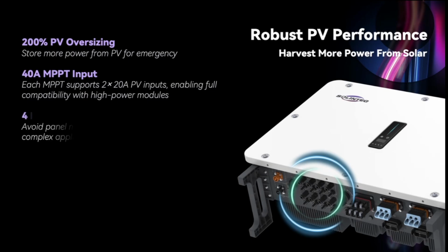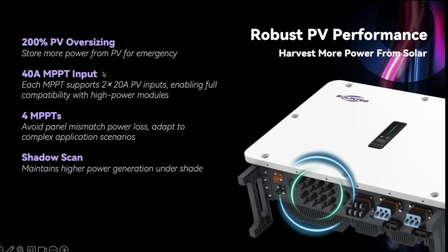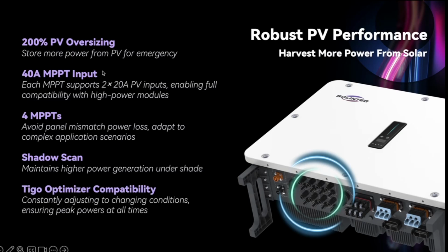We also provide 4 independent MPPTs, which can help to minimize mismatch loss and adapt to multi-direction or partially shaded installations, which is very common in C&I projects. To further boost generation under shade, the system also supports the shadow scan function and the optimizer capability, ensuring your array will always perform at its peak, even in challenging site conditions.